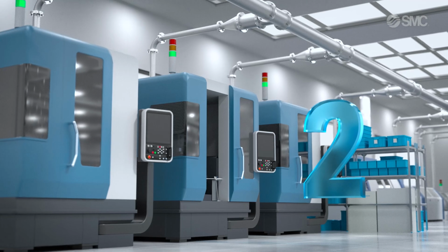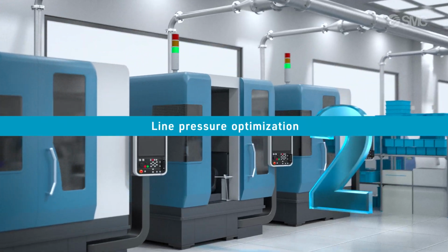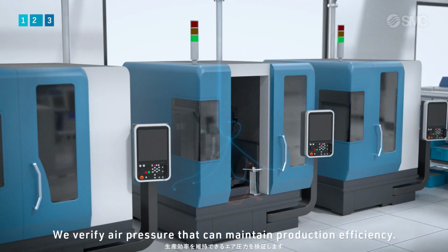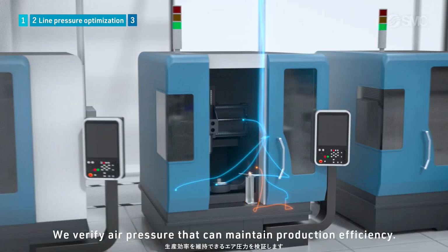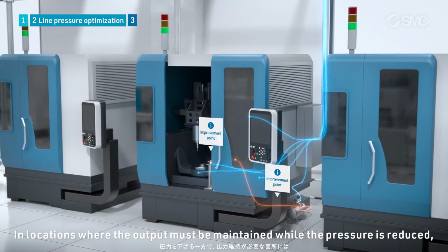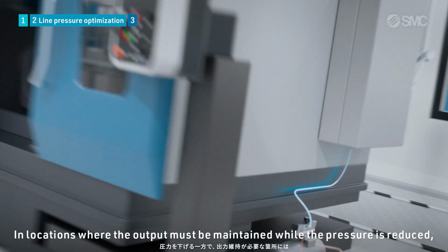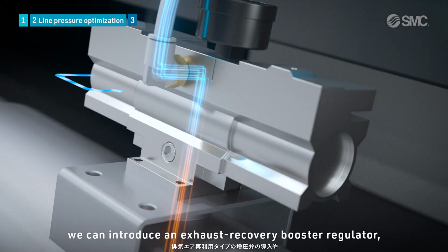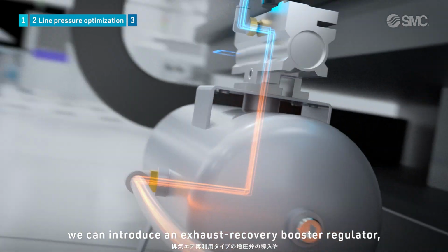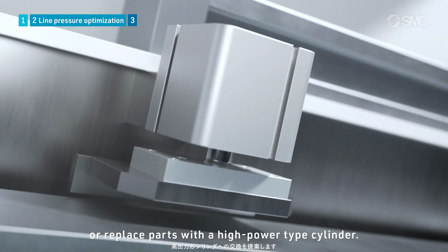Step 2. Line pressure optimization. We verify air pressure that can maintain production efficiency. In locations where the output must be maintained while the pressure is reduced, we can introduce an exhaust recovery booster regulator or replace parts with a high-power type cylinder.